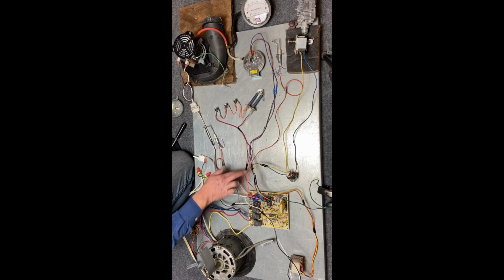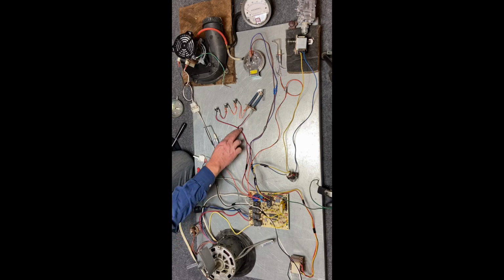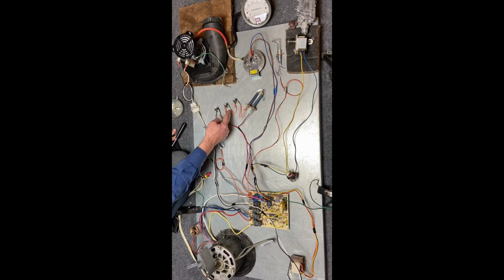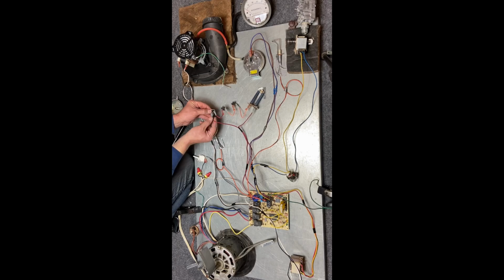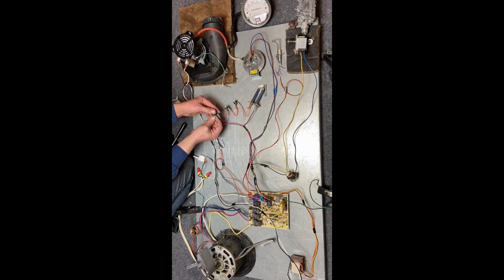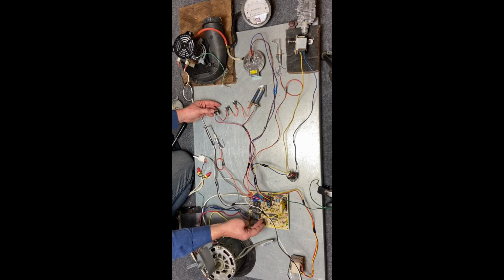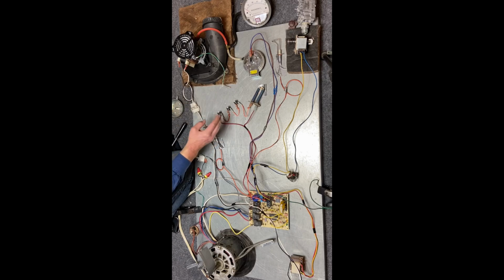Over here we have 2 more wires going to this multiple plug, but it's 2 wires and it wires in series through multiple limits. We go into, out of, into, out of, into, out of, into, out of, and all the way back home. So it's 2 wires, again, 2 wires, 2 wires, 2 wires, and 2 wires. Quite simple. These are limit switches, they're manual limits, and these are specifically rollouts. So if the flame was to roll out of the heat exchanger, it would cause this bimetal to trip. When the bimetal tripped, then it's going to open the wires and the control board knows that one of these safeties have failed. When we come out, we push this button and it resets it, but if the flame rolled out of the heat exchanger, we want to know why before we just press that button.